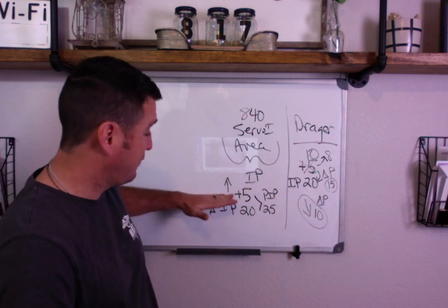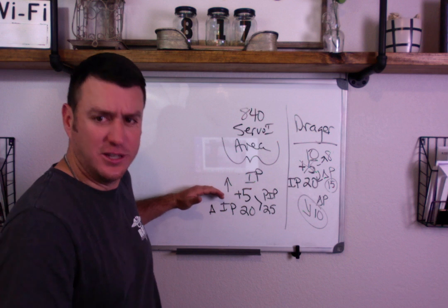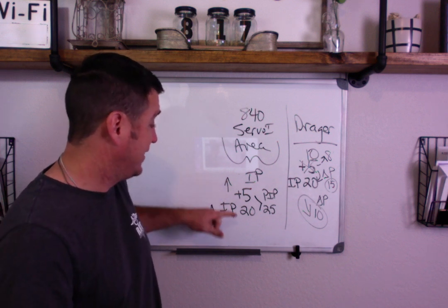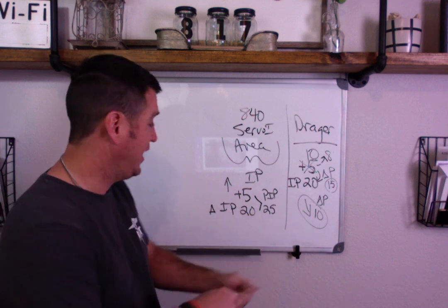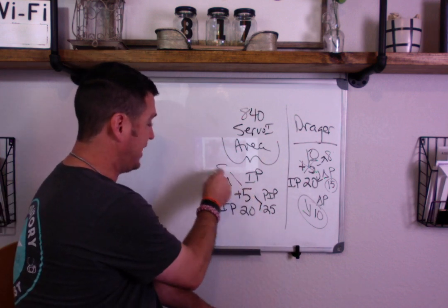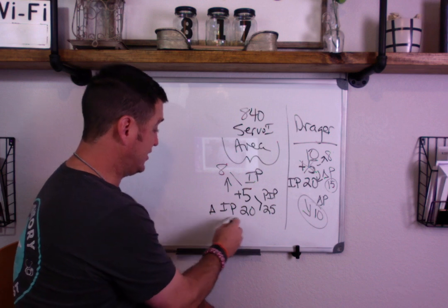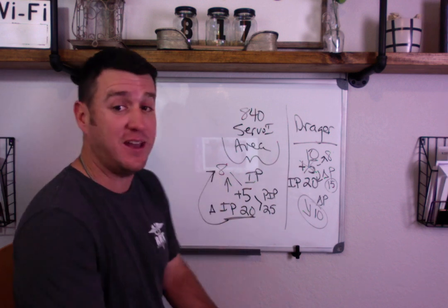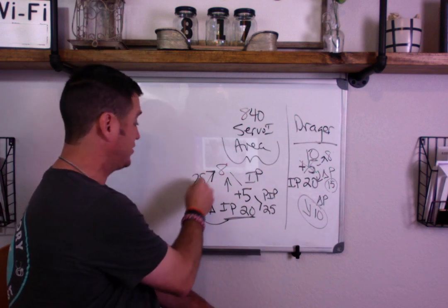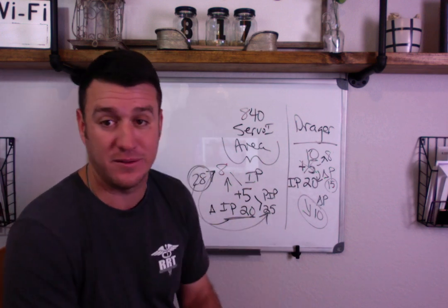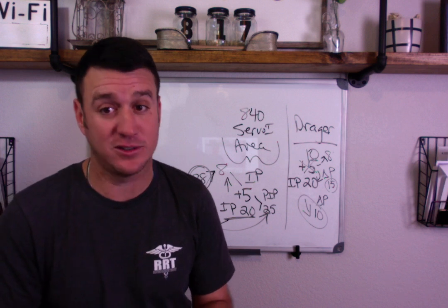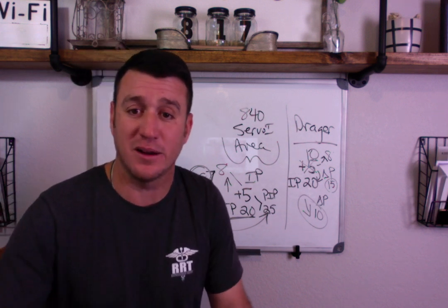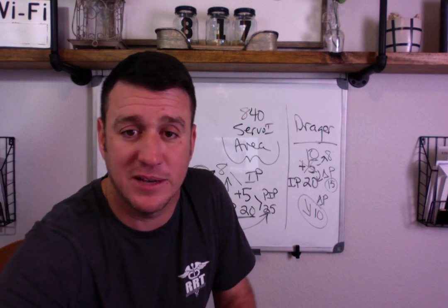Auto PEEP will not affect the amount of pressure delivered on a delta P ventilator — it just raises the PIP instead. If auto PEEP goes up to 8, you're still adding 20 cmH2O, so your PIP becomes 28 instead of 25. You need to ask yourself why. Set your peak inspiratory pressure, maneuver it to achieve 6 to 8 mLs per kilo — 4 to 6 for ARDS. Know your equipment, because they function differently. Hope I answered your questions and hope everybody's having a great day.